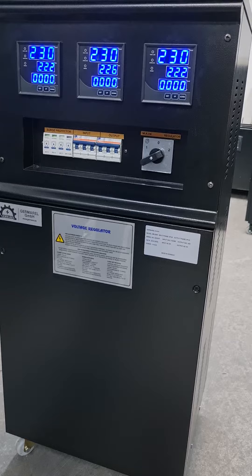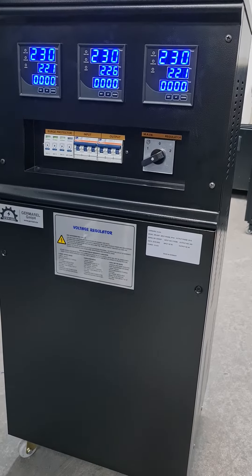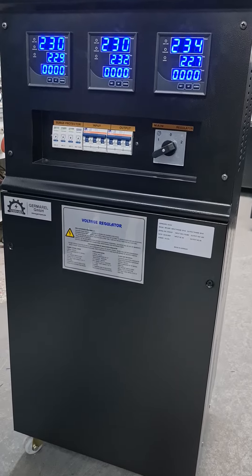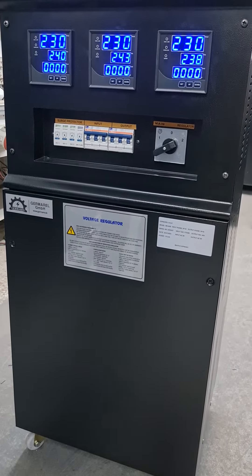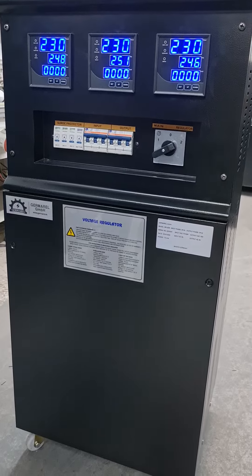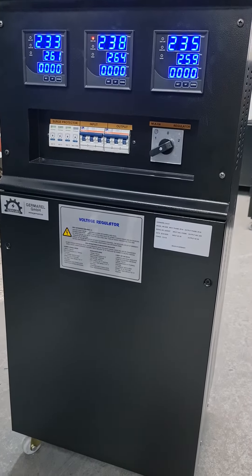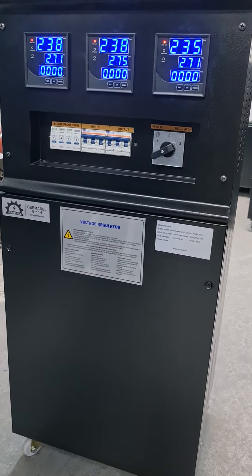Now we will test the device with decreasing and increasing input voltage. First, we increase the voltage up to its regulation range. When the voltage is out of its range, the device will protect itself and the contactor will cut off the output.